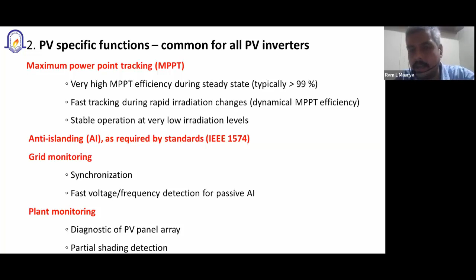Then you have to do anti-islanding. Anti-islanding means if suppose the grid is down, then your solar power should also be down. It should not supply the grid. If there is a loss of power in the grid, you should be down. You should not keep on generating. There are many such requirements. This is the IEEE 1574 standard.